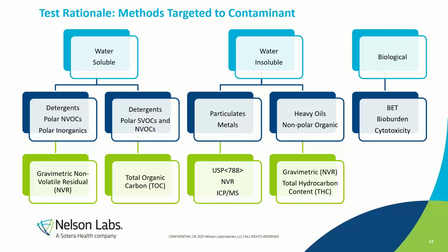So looking at this table, kind of from left to right at the bottom, you can see gravimetric non-volatile residue and TOC, both under the water-soluble category. And we're going to dig into these a little bit more on later slides, but the gravimetric non-volatile residue method is strictly non-volatiles. It does have an evaporation step involved. So any semi-volatiles like IPA are going to be lost in that process. But it's not specific to organic or inorganic. If there is sodium hydroxide or nitric acid on your device, that's going to be extracted and detected in that non-specific measurement, as well as detergent residuals, as well as if you have metal flakes on the device, that's also going to come off in the gravimetric water extraction. So it's a broad scope of potential residue, which has pros and cons, right?